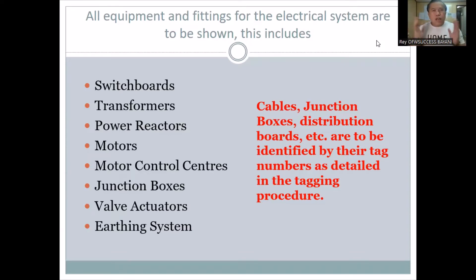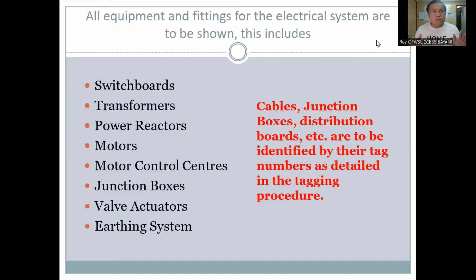The question was: how do you inspect the installation of a panel — for example, switchgear or panel board? What would you base it on? I said: installation details, general arrangement drawing — because everything is there in the general arrangement drawing. And are the materials approved? He said I was still missing something. I said: general arrangement drawing, installation details, location layout — that's already there. It turned out what I was missing was identifying the tag number on the panel. I said that's automatic — it's in the general arrangement drawing. When you check it, the tag number is right there.